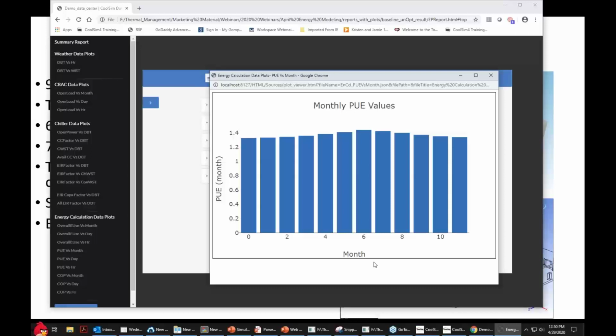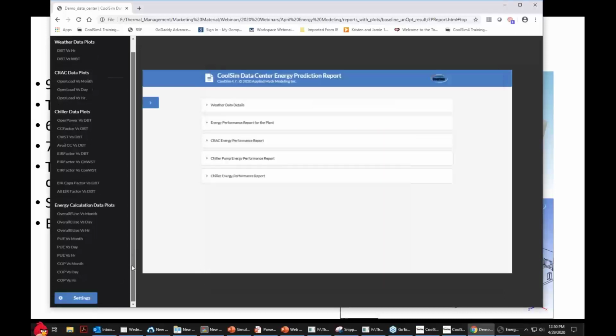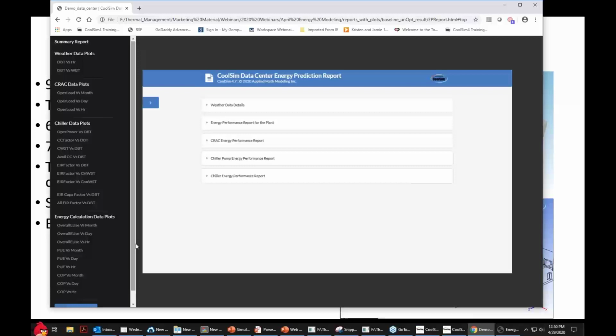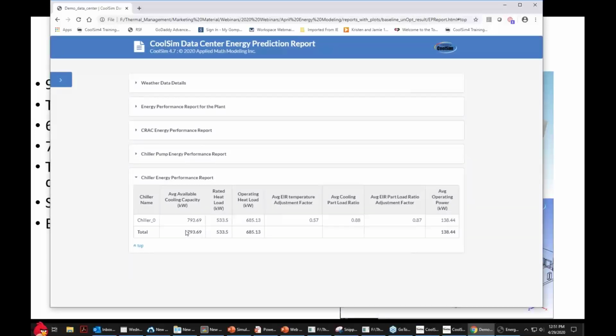We had a question about whether the chiller is cooled by water or by air. That was an air-cooled chiller, I believe, that we were looking at there. In the models that we developed, we have air chillers and water chillers. And in the case of each one, we have different types of compressors. So for an air-cooled chiller, there will be a scroll, a screw, and a reciprocating. And for a water-cooled chiller, there'd be those plus a centrifugal chiller as well. So the correlations take into account whether it's air or water, and also what type of compressor is being used in the chiller.